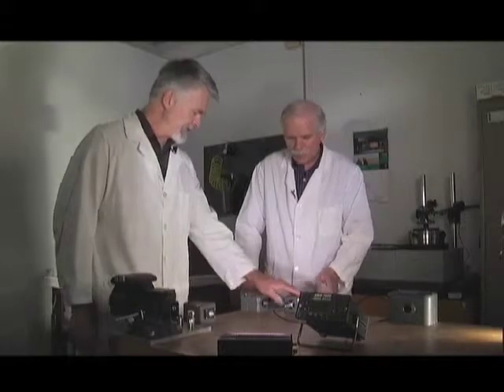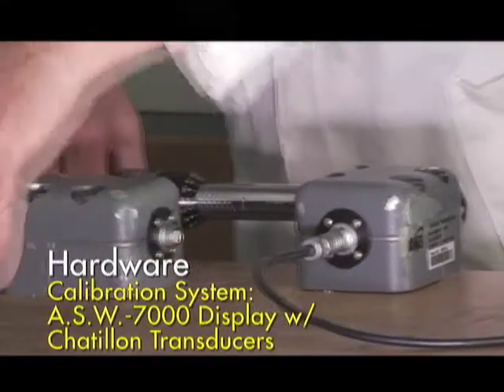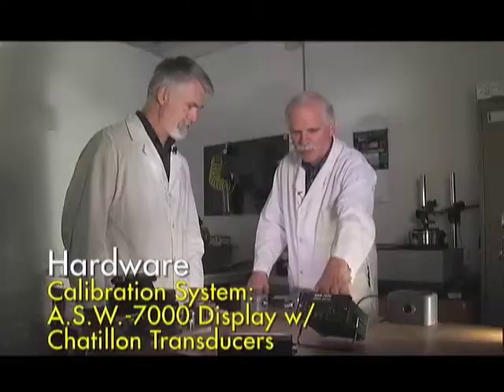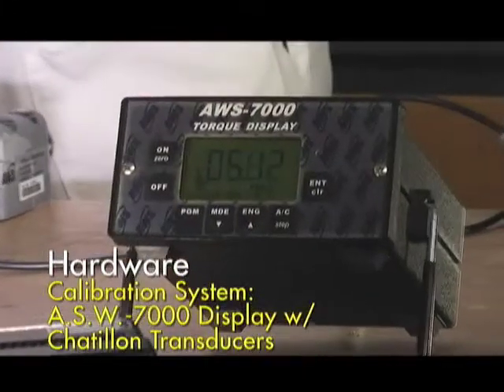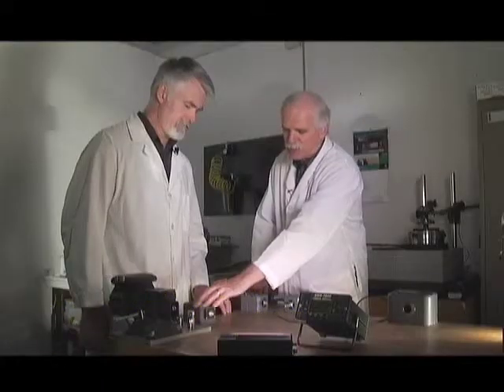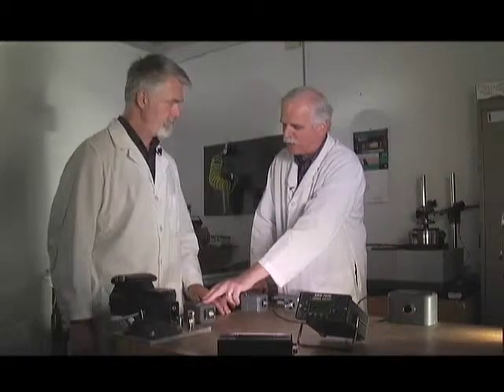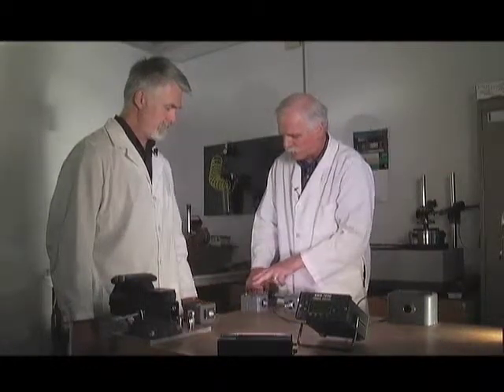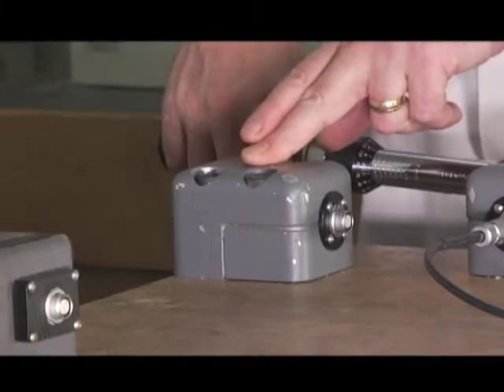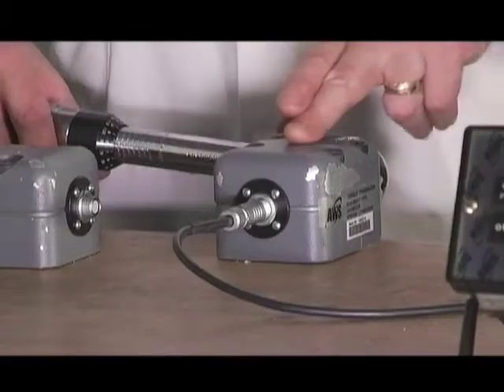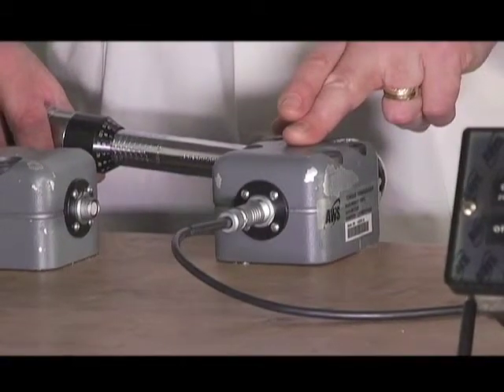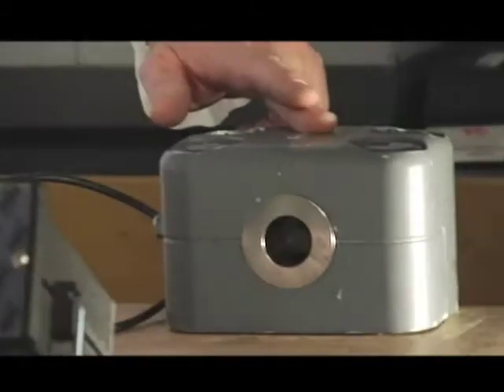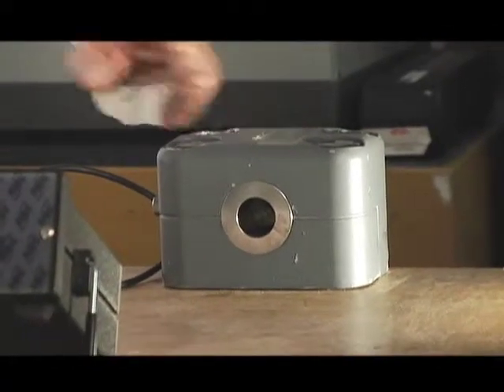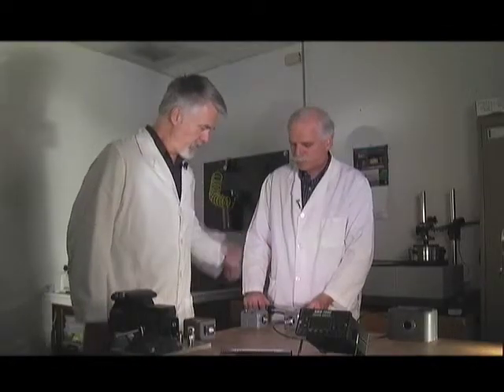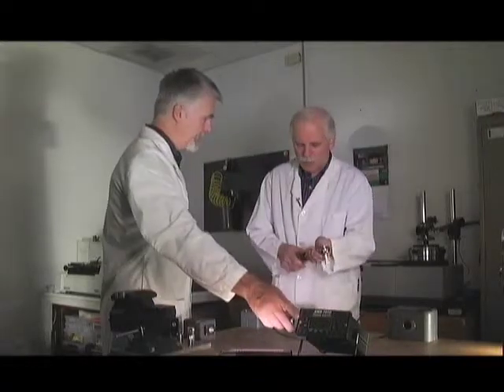And what are we looking at here? These are torque transducers, and they're hooked up to our display, and this display measures the torque. This transducer is set for inch-ounce. This one goes from 10 inch-ounce to 100. This one goes from 10 inch-pounds to 100 inch-pounds. This one goes from 10 foot-pounds to 100 foot-pounds. And this goes from 60 to 600 foot-pounds. And as you're torquing on this, it's giving you a torque reading. It'll give a readout, okay.